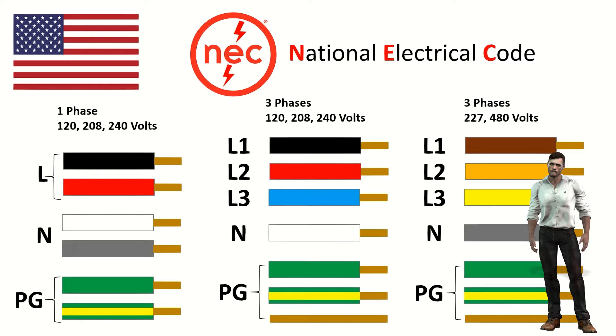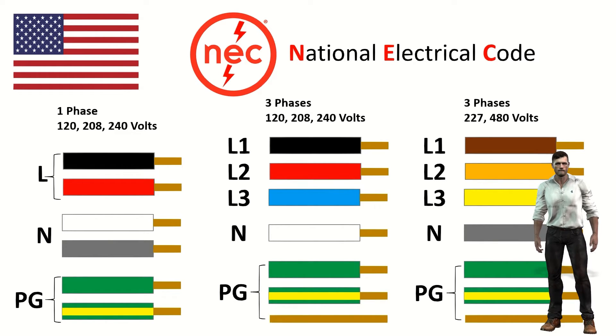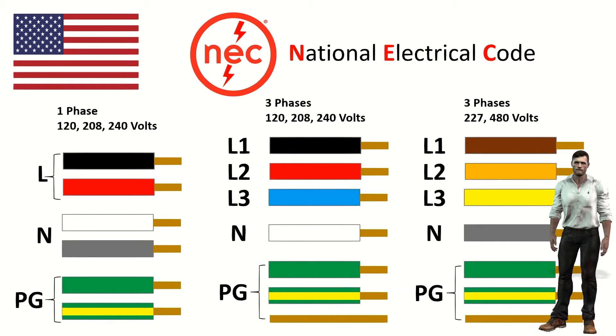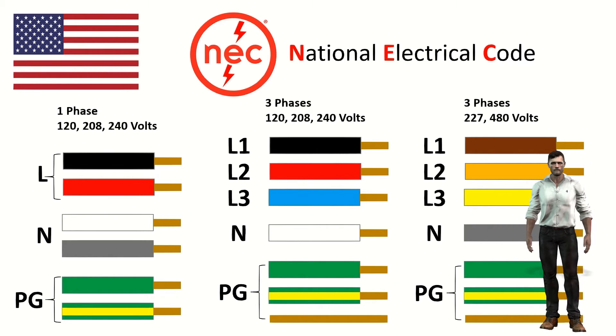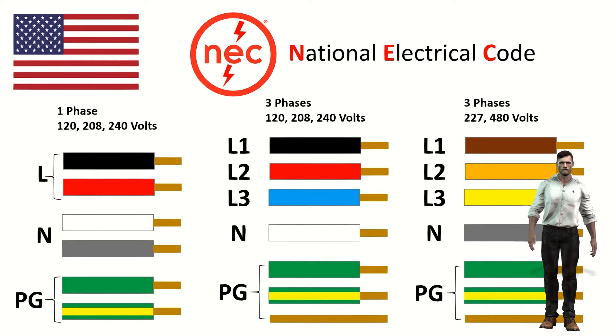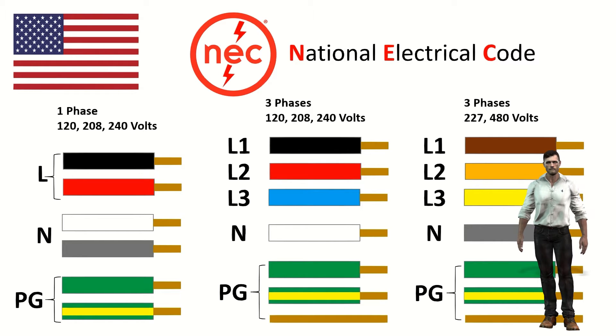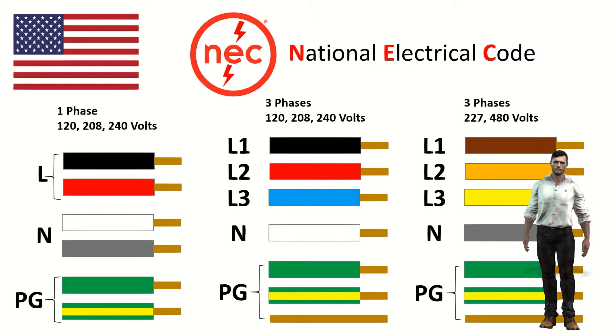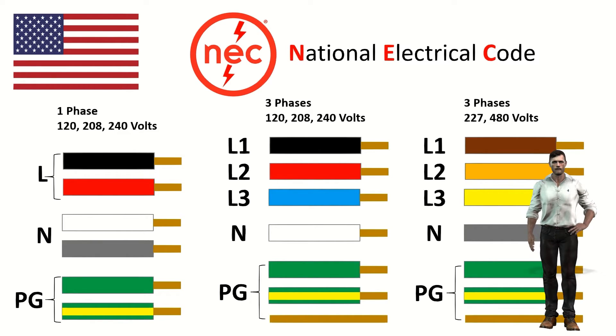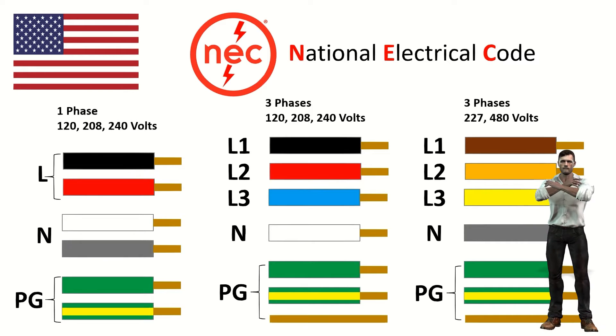Let's start with the United States. The National Electrical Code recommendations establish, for both AC and DC voltages, the color white or gray for the neutral grounded, and the colors green, green with yellow, or bare copper for the protection ground. Active cables can be of any other color except those already mentioned. For single-phase alternating voltage installations with nominal voltages of 120, 208 or 240 volts, typically used in residential and office installations, black or red is used for the line cable (L), white or gray for the neutral wire (N), and green or green with yellow for the protection cable or ground wire (PG).